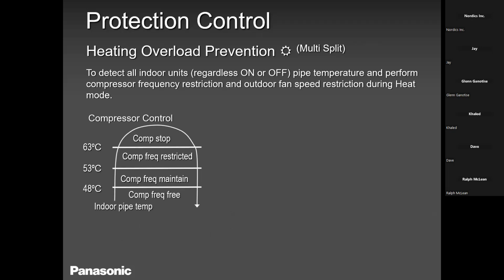Heating overload prevention. This is another protection to take care of the compressor and to detect any indoor units overheating. You know, sometimes when the indoor coils get very hot, the pressure tends to rise higher and higher, because keep in mind, in heat mode, your indoor units become the outdoor unit and your outdoor unit becomes the indoor unit. So sometimes when only one unit is running instead of all three or all two or all four or all five, the space area for that little coil, just one indoor unit, is not enough, you know. So it tends to cause high pressure. So in that case, we have a protection as well, which is basically H98.